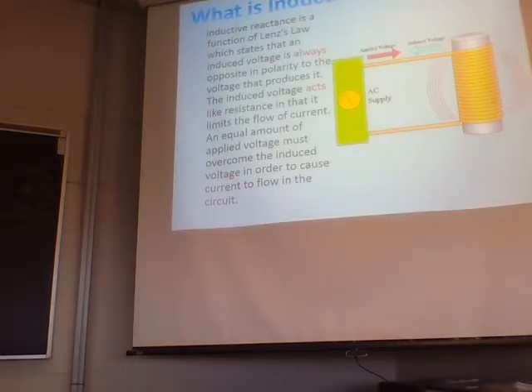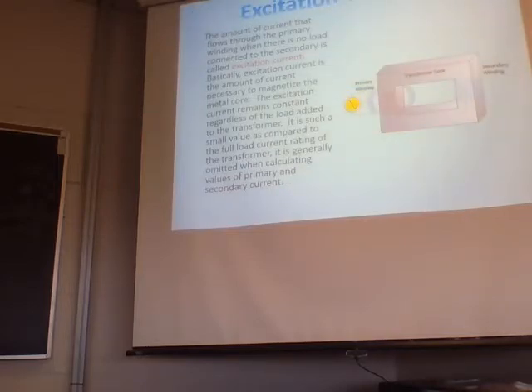The amount of current that flows through the primary winding when there is no load connected to the secondary is called excitation current. Basically, excitation current is the amount of current necessary to magnetize that metal core. The excitation current remains constant regardless of the load added to the transformer. It is such a small value compared to the full load current rating of the transformer that it's generally omitted when calculating values of primary and secondary current. That's excitation current. That's not inrush.